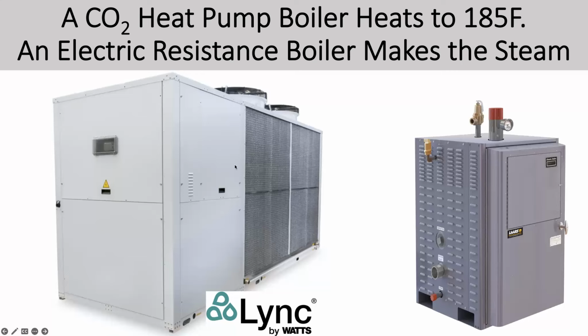So here we have a CO2 heat pump, which can go from -30 Fahrenheit all the way up to 185 Fahrenheit. So -30 weather outside, a super polar vortex, and you're producing 180 Fahrenheit water. That's not boiled yet — it has to go into an electric resistance steam boiler. This is for steam heating systems, and this is what you call a cascading system, or 2 lifts.